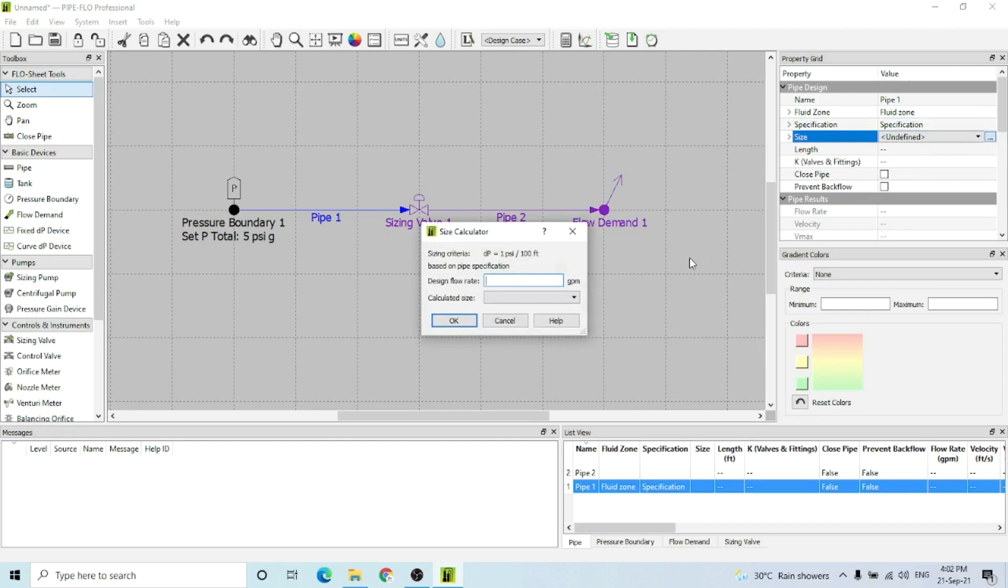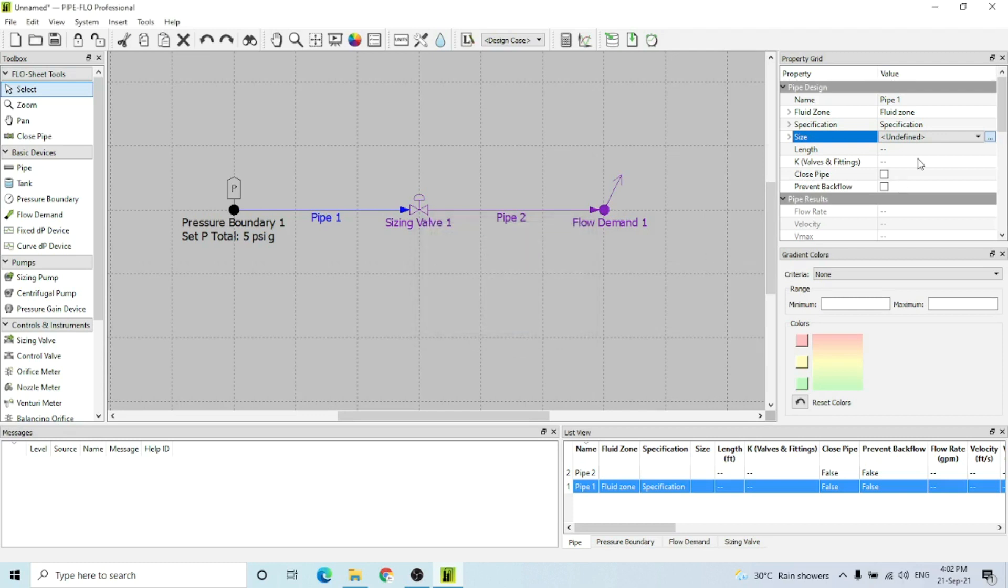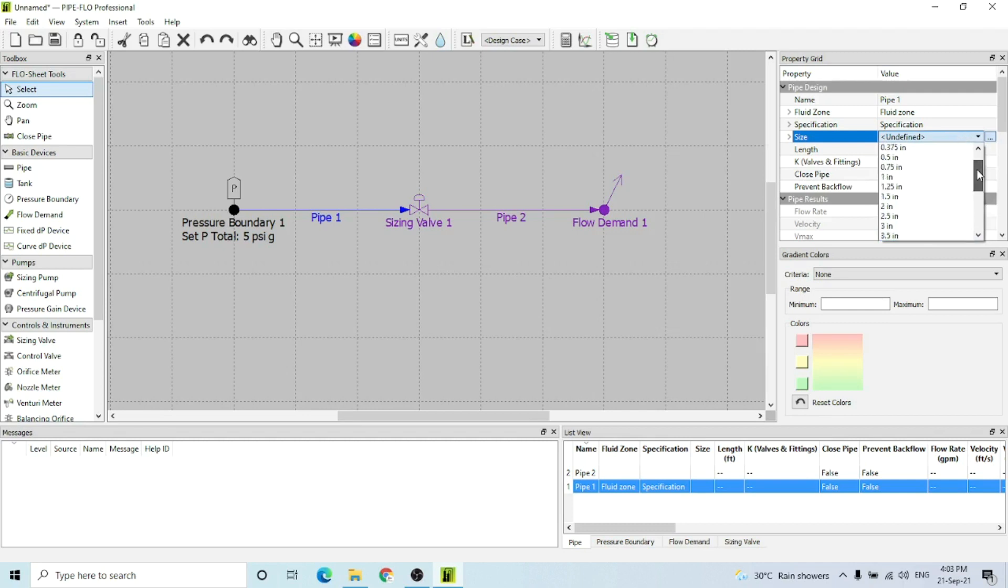Then Pipe 1. You have to select the fluid zone and then pipe specification. After that, the size - you can select the size or calculate it as per your sizing criteria. For example, if I enter a design flow rate of 10 gpm, the software has calculated 1.25 inches size for this pipe at this sizing criteria.